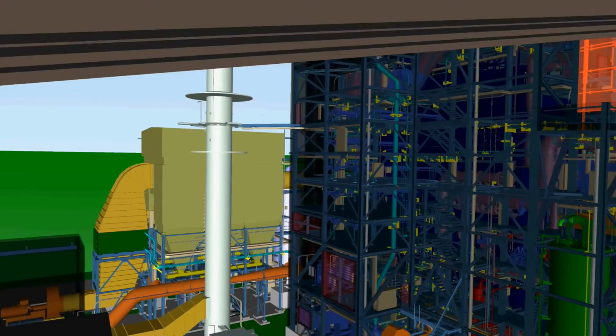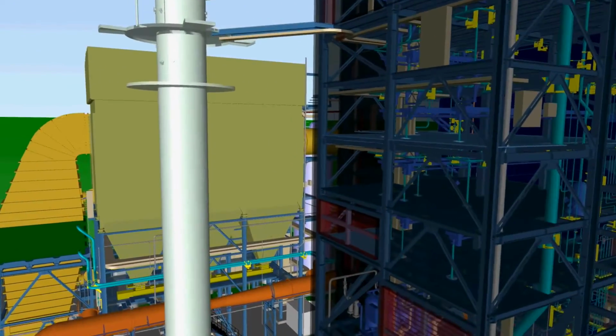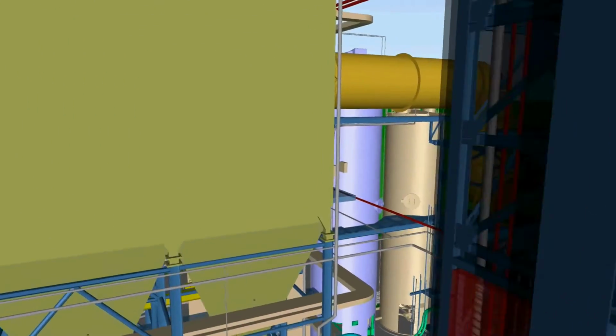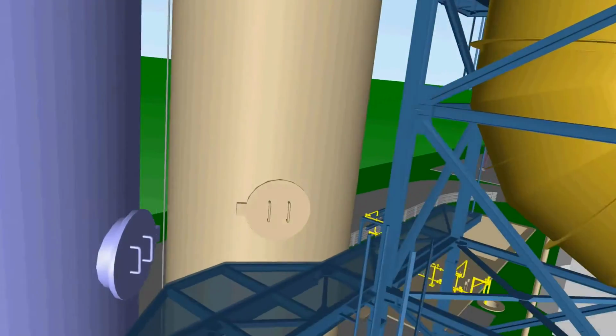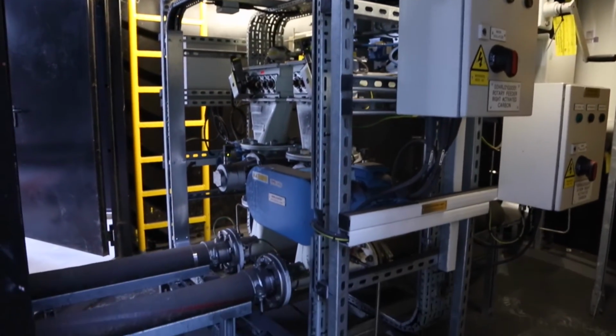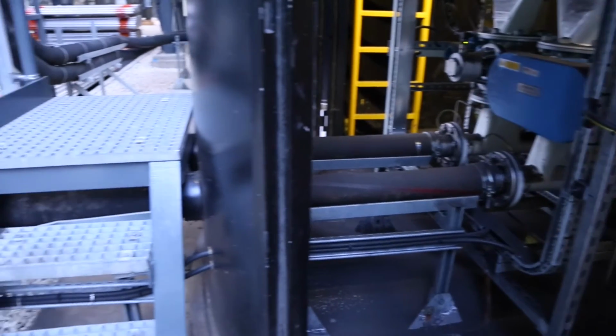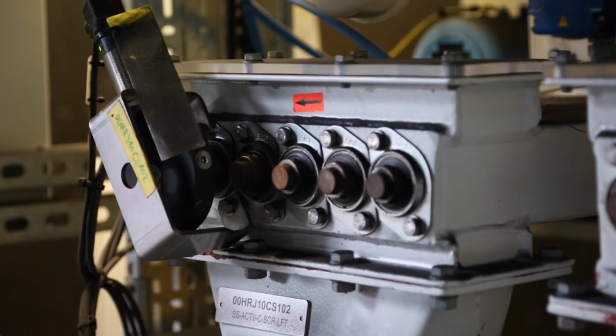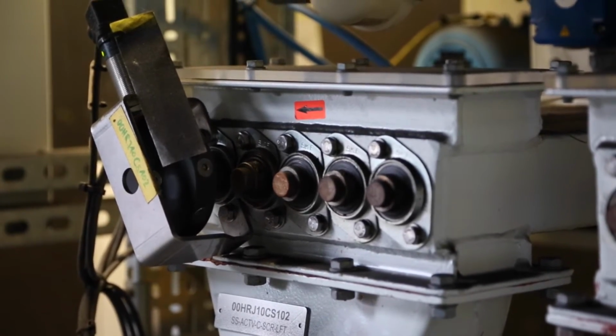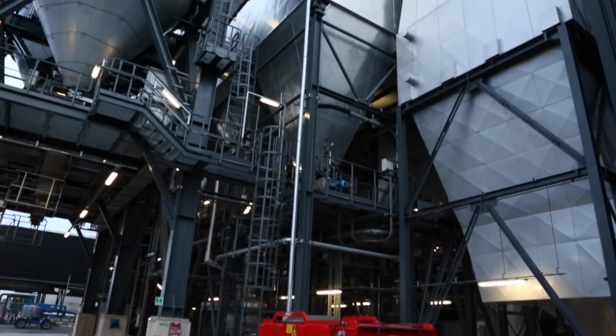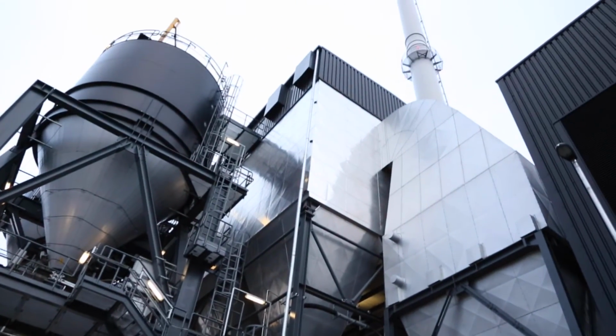This requirement from the Waste Incineration Directive 2000/76/EC is fulfilled in the range described in the diagram. Activated carbon is injected downstream the economizer, reacting with all kinds of heavy metals, dioxins, and furans. The reaction products are extracted downstream in the bag filter.